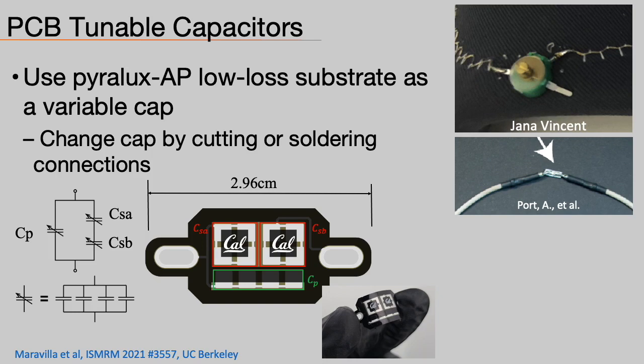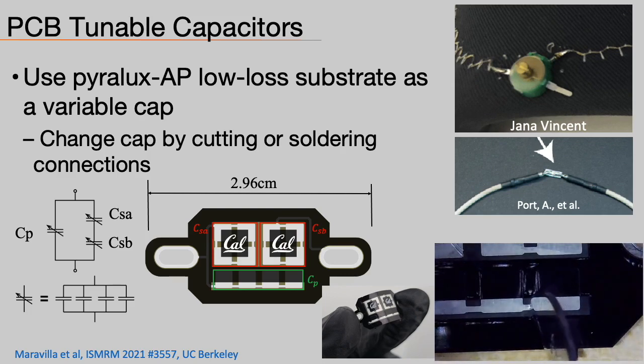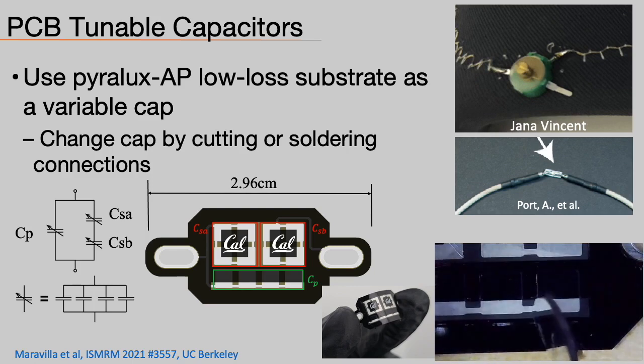Variable trim capacitors are often used by coil designers — they make it easy to tune and match without needing to solder and desolder rigid capacitors, which may not be possible when using novel conductors and substrates. This work from our group presents a flexible variable capacitor constructed with series and parallel plate capacitance for rough and fine tuning. We use a low-loss Pyralux AP flexible PCB. Tuning is done by cutting or soldering traces on the capacitor, mimicking the use of a trim cap but maintaining flexibility.